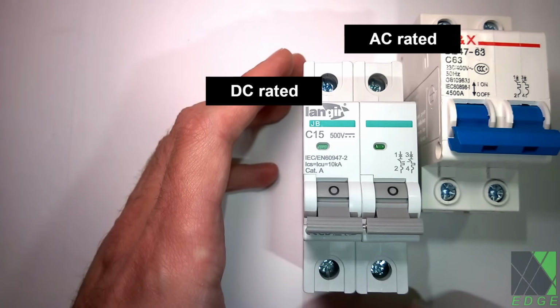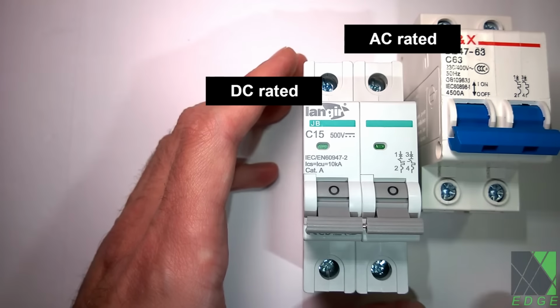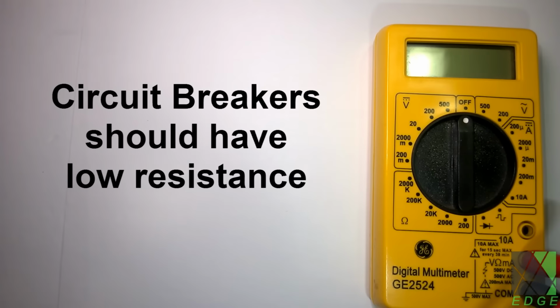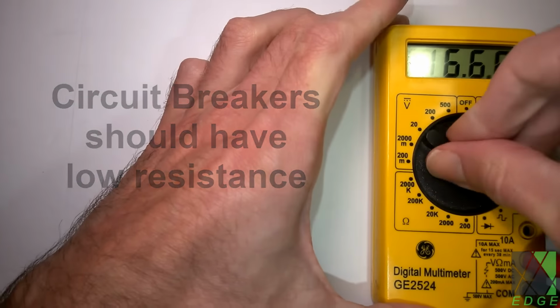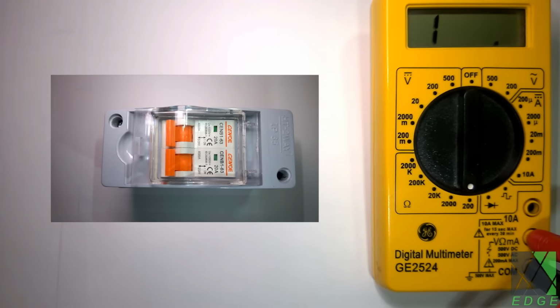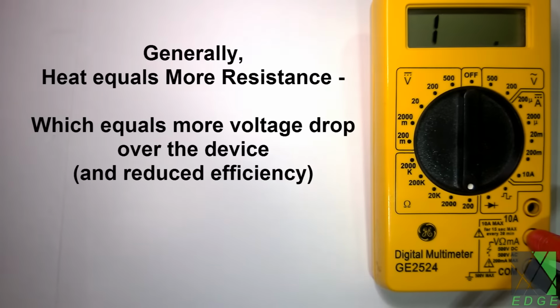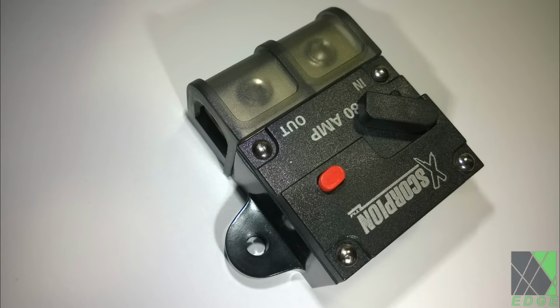Watch out for dishonest sellers listing AC circuit breakers as DC PV solar rated. Use an ohmmeter to check new and existing circuit breakers for high resistance. This is a good idea. There should be very little resistance across the breaker, otherwise the breaker is suspect. If you are concerned about the resistance of the protective device and its efficiency, consider the following. The hotter a circuit breaker gets, generally, the greater its potential resistance and so the lower its efficiency. Believe it or not, a circuit breaker should be kept as cool as possible.